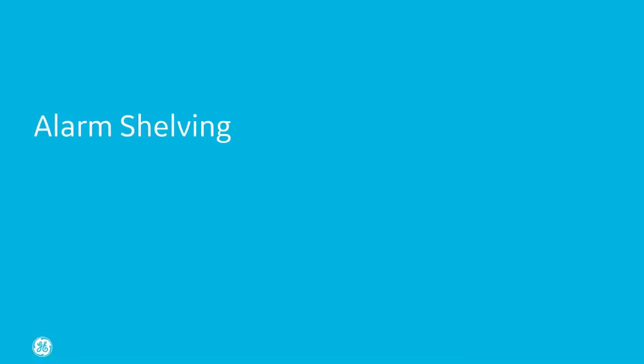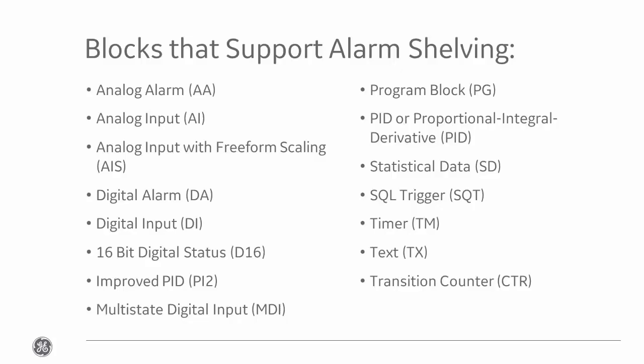Alarm shelving. Now this one's a little more involved. We're going to be looking at new UI in both the database manager and the iFix workspace. Here's a list of blocks that currently support alarm shelving. Alarm shelving is all about making it easier for the operator to troubleshoot issues, temporarily removing nuisance alarms.